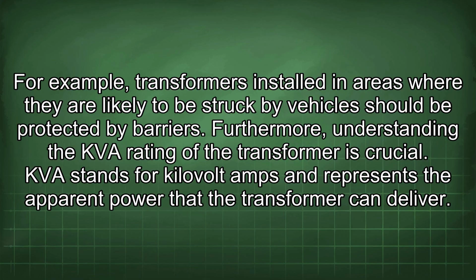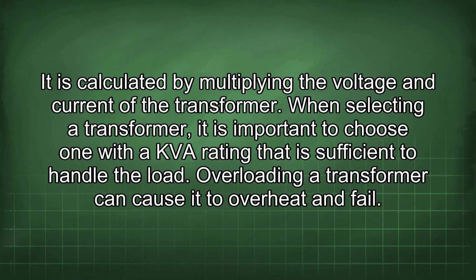Furthermore, understanding the kVA rating of the transformer is crucial. kVA stands for kilovolt amps and represents the apparent power that the transformer can deliver. It is calculated by multiplying the voltage and current of the transformer. When selecting a transformer, it is important to choose one with a kVA rating that is sufficient to handle the load. Overloading a transformer can cause it to overheat and fail.